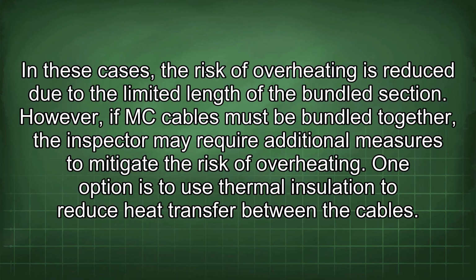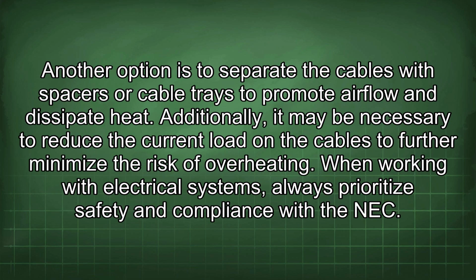However, if MC cables must be bundled together, the inspector may require additional measures to mitigate the risk of overheating. One option is to use thermal insulation to reduce heat transfer between the cables. Another option is to separate the cables with spacers or cable trays to promote airflow and dissipate heat. Additionally, it may be necessary to reduce the current load on the cables to further minimize the risk of overheating.